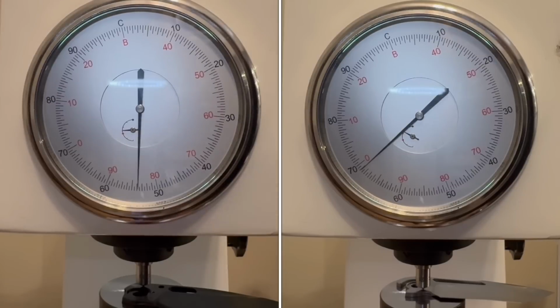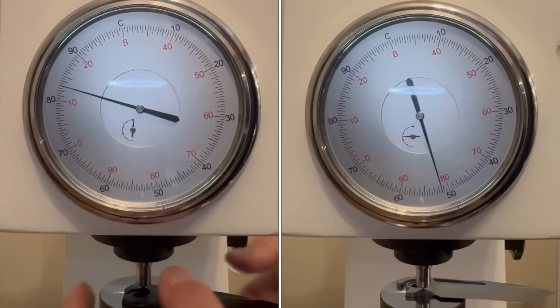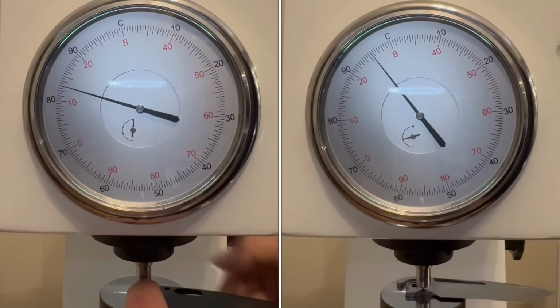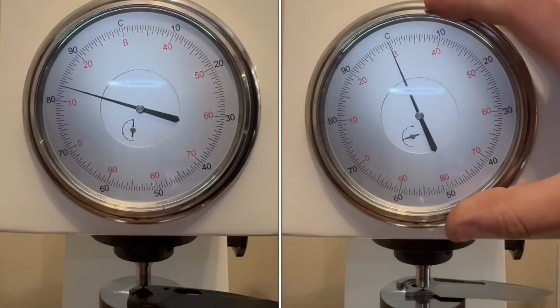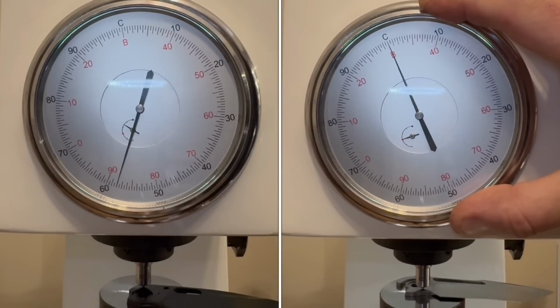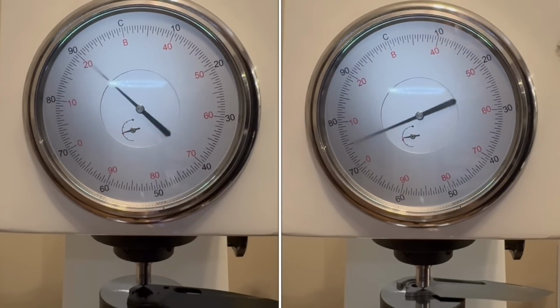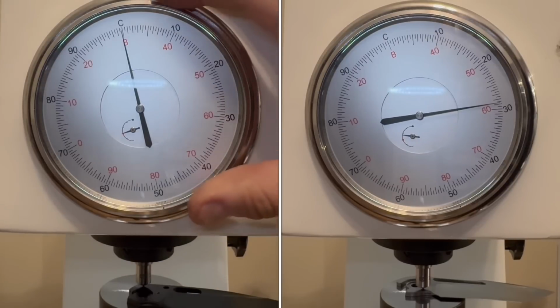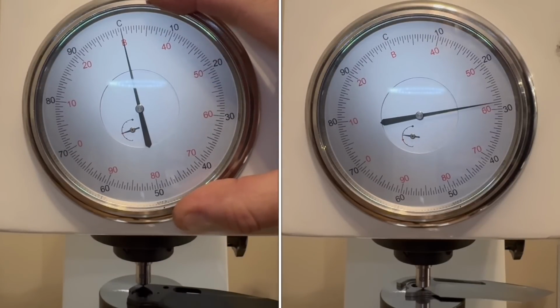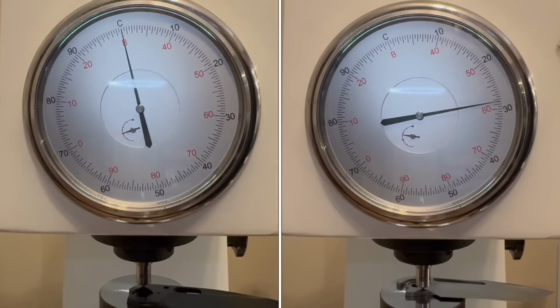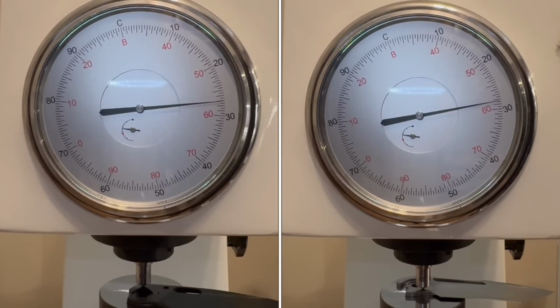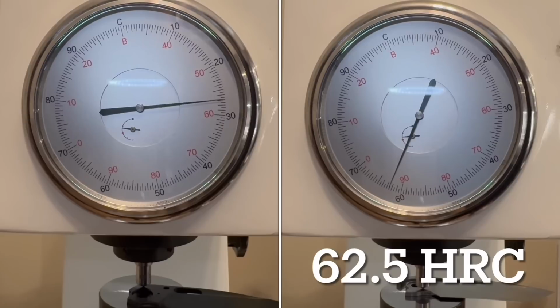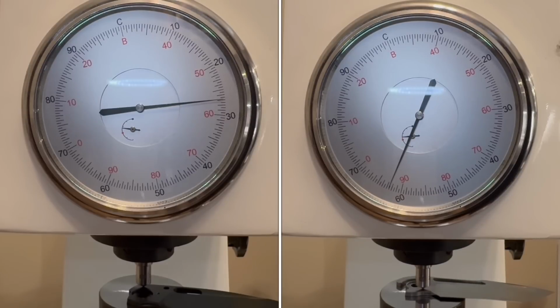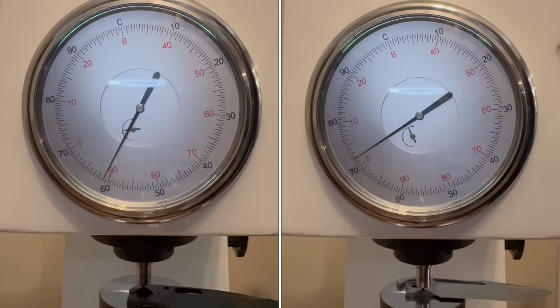Okay, let's set up on the right to test the Offender again. Setting up the 0 here on the right. And we're going to do the same on the left as well. So it's confusing to me. Maybe you'll have to watch it a couple of times and just look at the left or at the right. Especially these pauses when the major force is applied for 12 seconds drive me nuts. But here you go. We're about ready to release the major force on the Offender. And we got 62.5 HRC. And time to check on the Excalibur on the left.